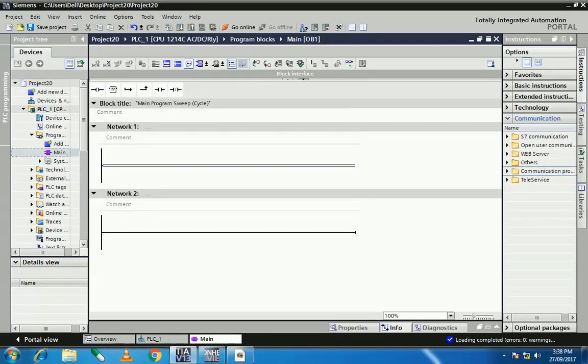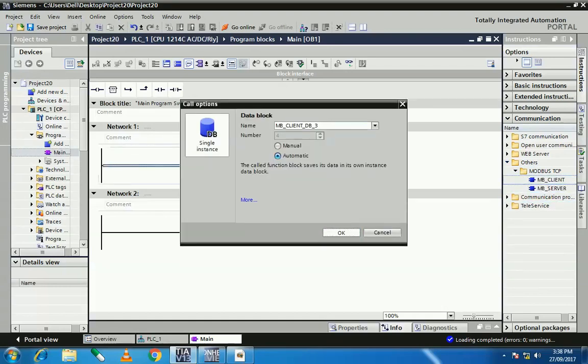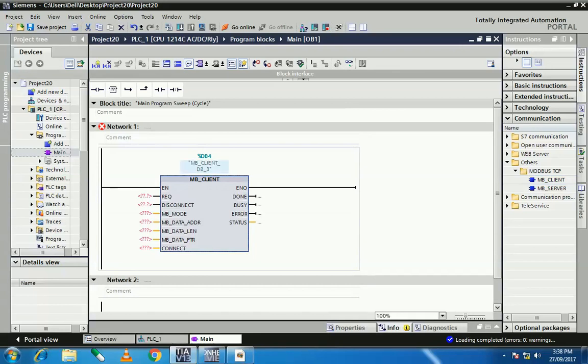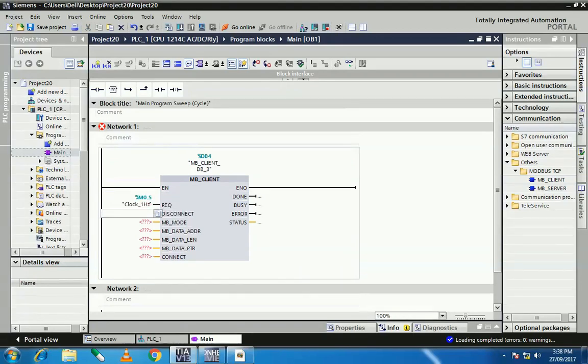Go to the communication block, open the others, Modbus TCP, and select the client block. This is the Modbus client block. This is your input data — REQ is the request bit, so I assign here one clock memory. When the request bit signal is high, your client block sends a request to the server for communication.